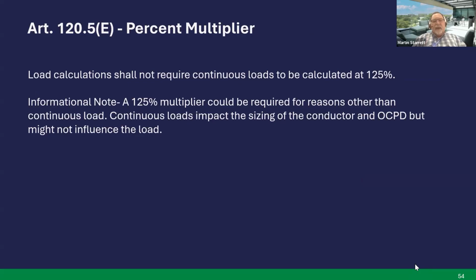Percent multiplier, 120.5E. Load calculation shall not require continuous loads to be calculated at 125%. The informational note says a 125% multiplier could be required for reasons other than continuous loads. Continuous loads impact the size of the conductor and the overcurrent protective device, but might not influence the load. So they're removing the 125% in the load calculation article, but it'll still be over in your sizing of conductor and also your sizing of your overcurrent protective device. Next slide, please.